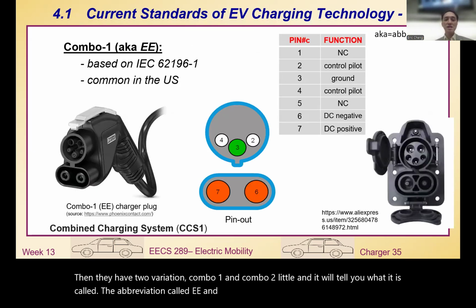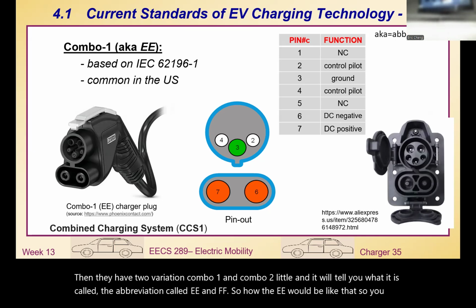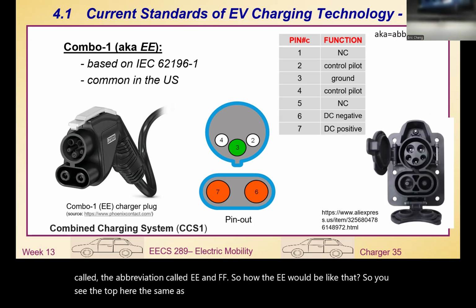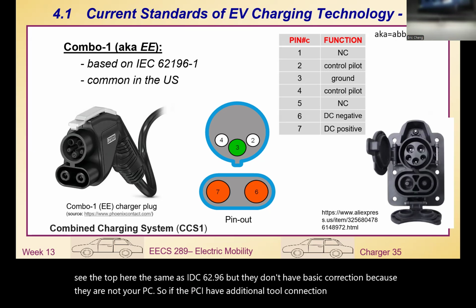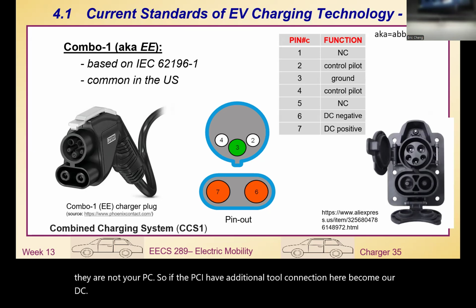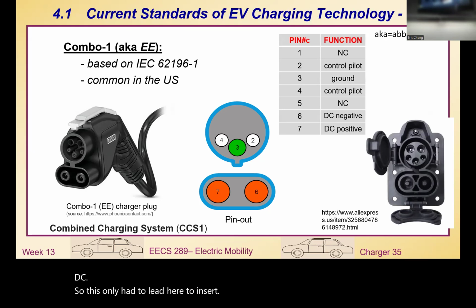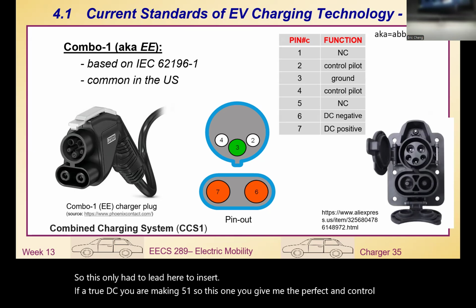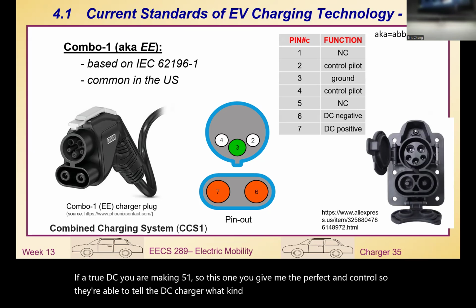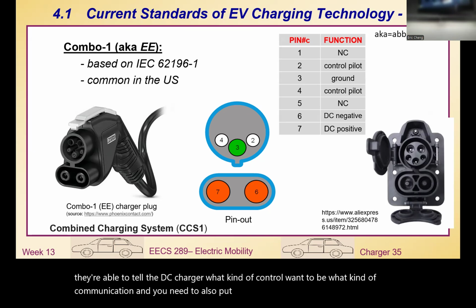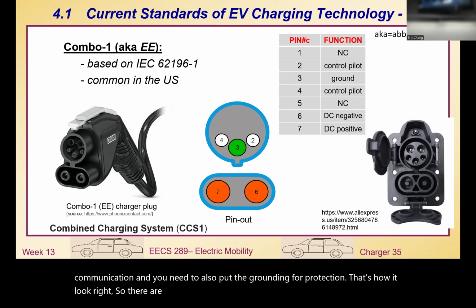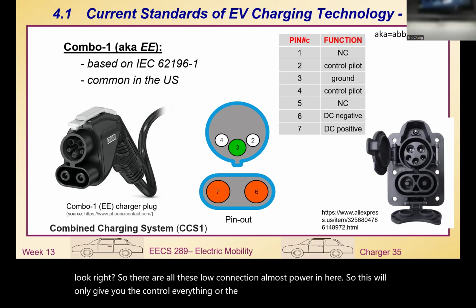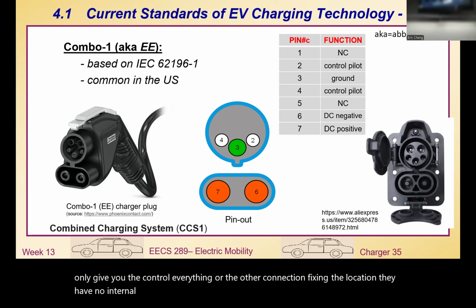So how does EE look? You see the top is the same as IEC 62196, but without the AC connection since these are now DC. The DC version has two additional connections added. This head is made easier to insert - the two DC pins fit around, while this part gives the earthing and control, letting it tell the DC charger what kind of control and communication you want, plus grounding for protection. That's how it looks. The low connection only carries power here, and this field gives you the control - everything else keeps a fixed location, with no internal connection there.